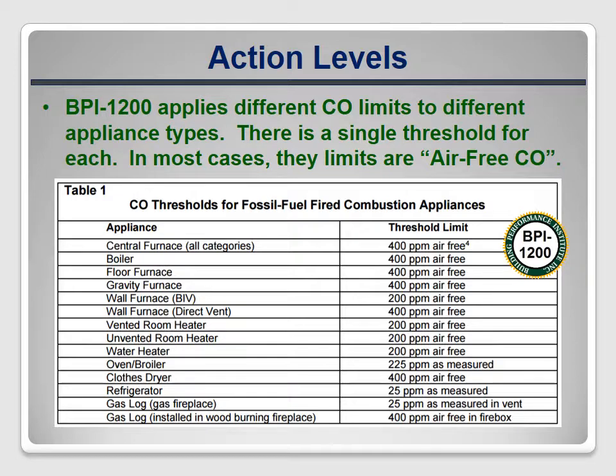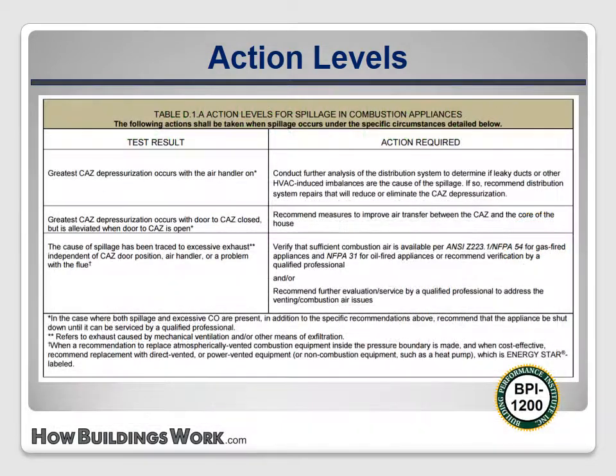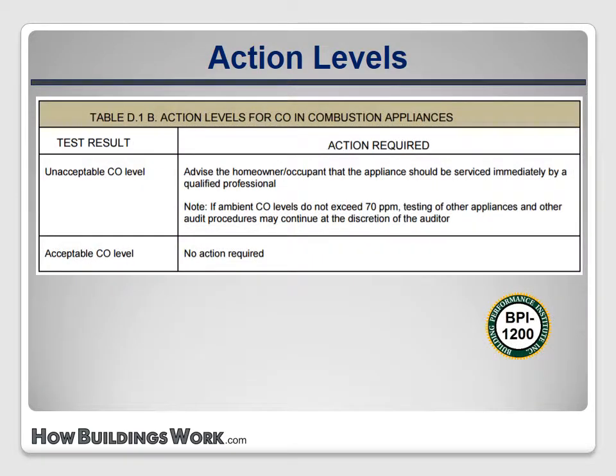BPI 1200's CO threshold table only sets the thresholds; the actions to be taken are listed in Annex D of the Standard. The spillage failure action table requires the auditor to diagnose the cause of spillage to determine the appropriate corrective action, which may require further analysis by the auditor or a qualified specialist. The carbon monoxide action levels table is shorter and simpler: if the CO level exceeds the threshold, the auditor should recommend that the appliance be immediately repaired by a qualified professional.